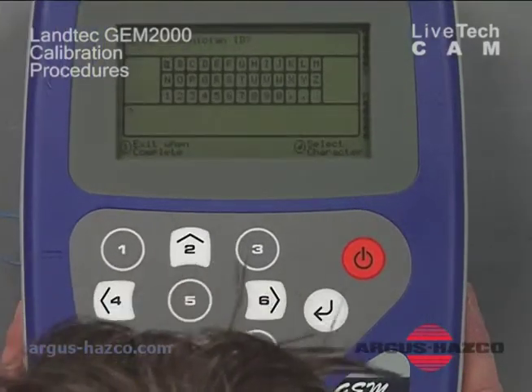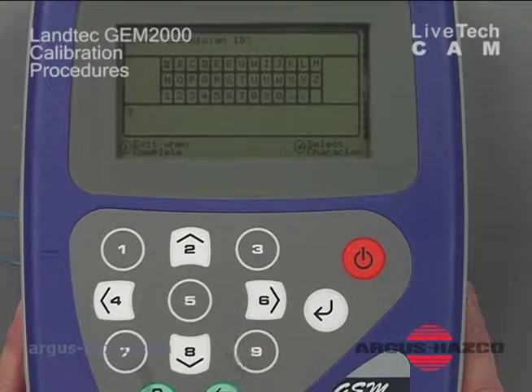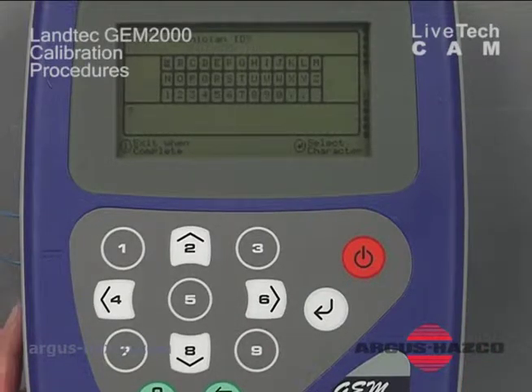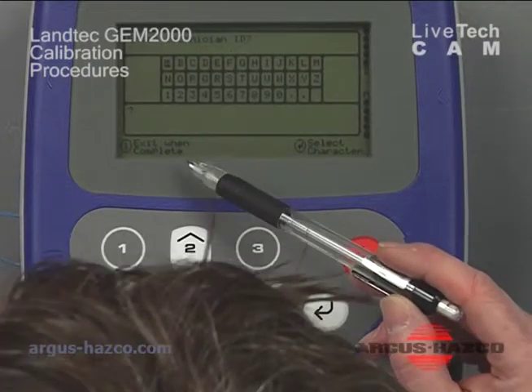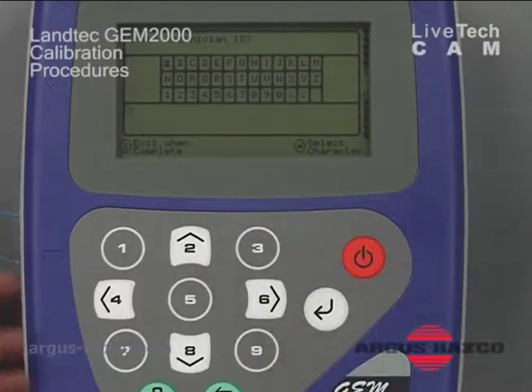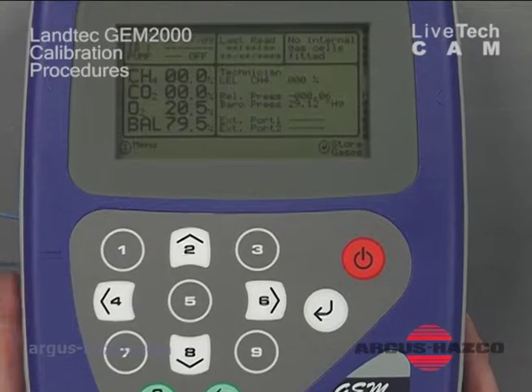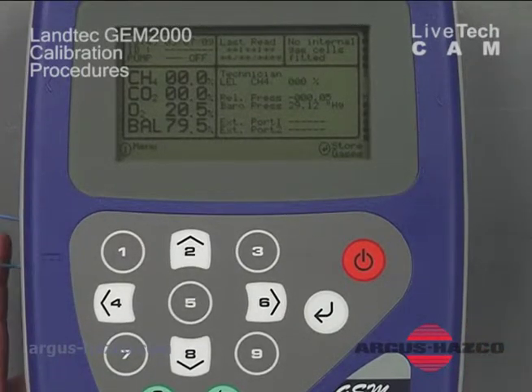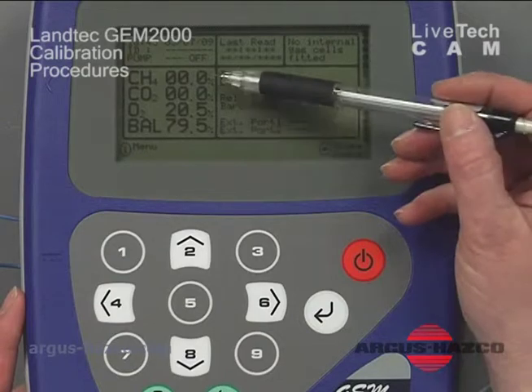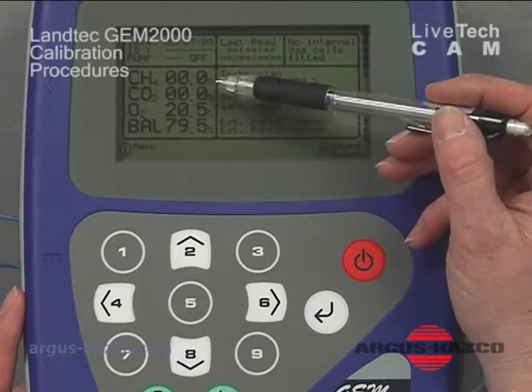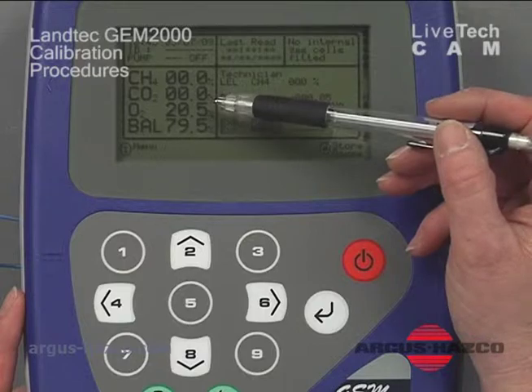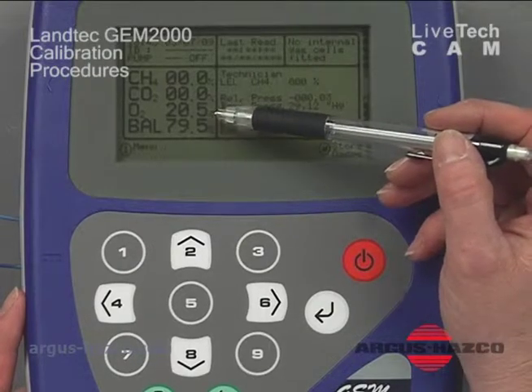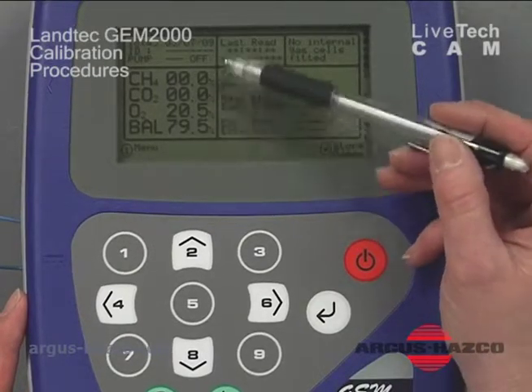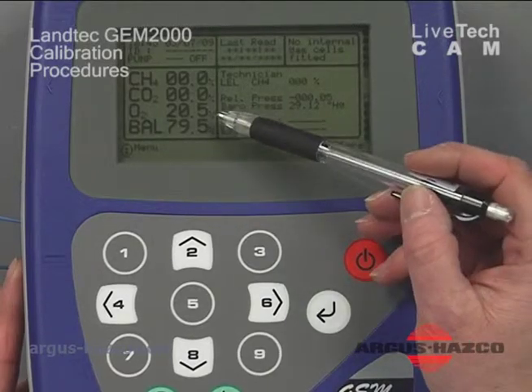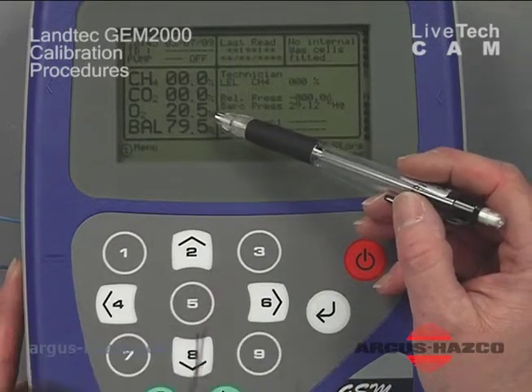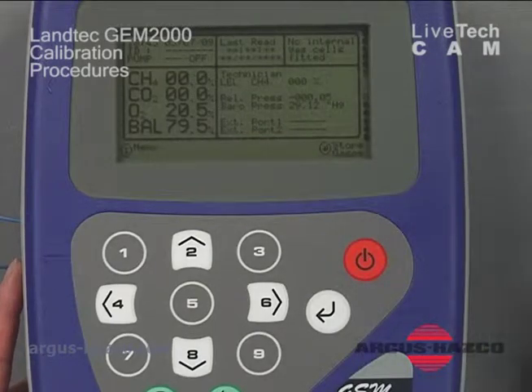And if we would like, we can enter our technician ID, but we don't want to enter any information at this point in time. So we go ahead and hit number 1 to exit when complete. Now we have our general readout screen. Along the left-hand side, you'll have your CH4 or your methane readings, CO2, carbon dioxide readings, oxygen readings, and then the balance of the gas. As you see right now, the unit is reading 20.5 oxygen, and the balance is 79.5%.